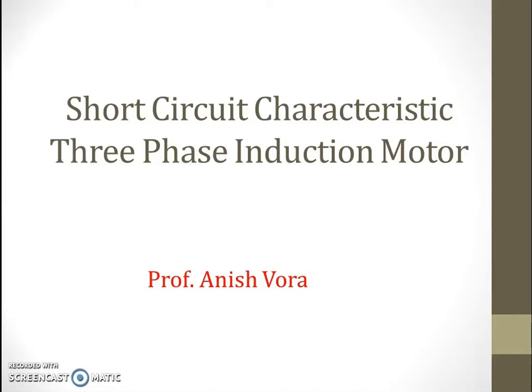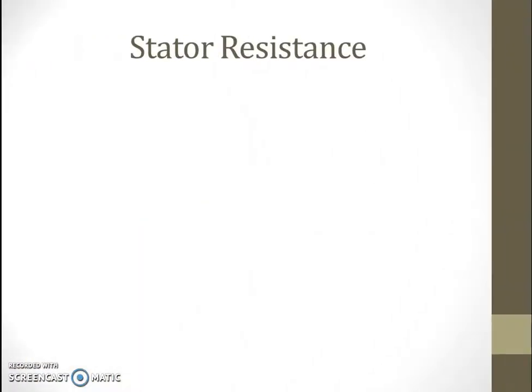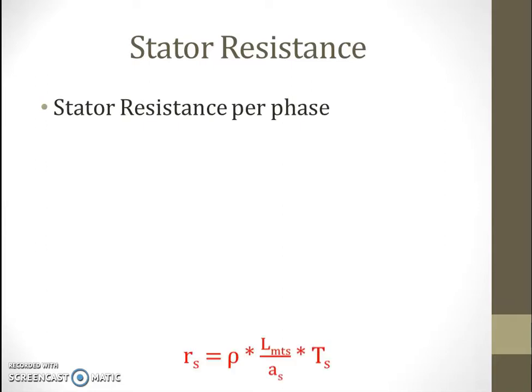We start with winding resistance — stator resistance. In case of three-phase induction motor, whether it is a wound type or squirrel cage type, stator resistance remains common because stator construction is common. Stator resistance per phase is given by rho multiplied by L (length of the mean turn) divided by cross sectional area, and multiplied by Ts that is stator turns.